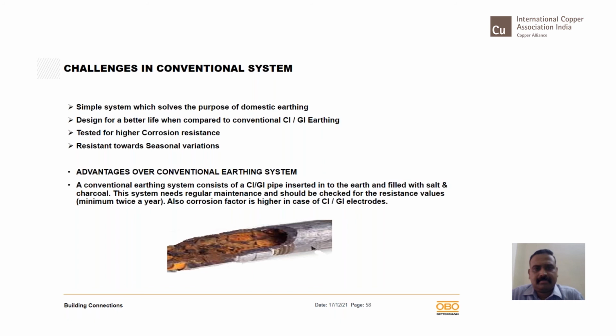Otherwise, every earthing, even the copper bonded with chemical earth being used, is also a conventional earthing system with a chemical added to it. Now, why did this transition between a CI or GI earthing and a copper bonded rod come in India? It is because the CI or GI rod is highly corrosive in nature, or corrodes faster than a copper or copper bonded system. And when it is implemented, people used to put it along with salt and charcoal inside. The nature of salt and charcoal will eat away the electrode, or rather erode the electrode, and over a period of time, there will be a disconnect inside this system.